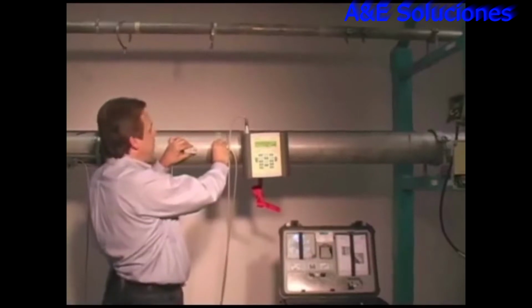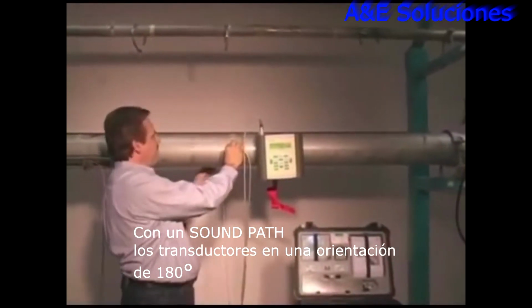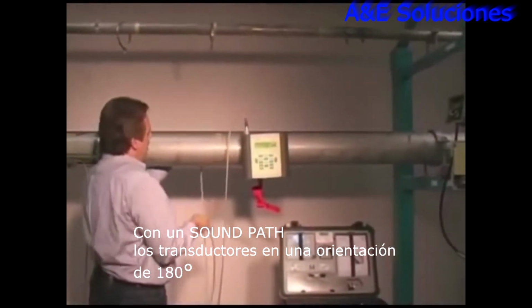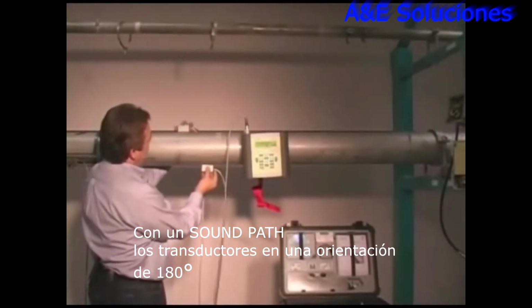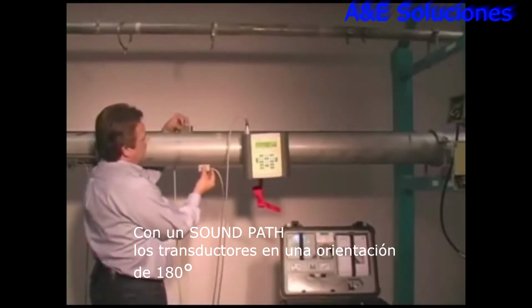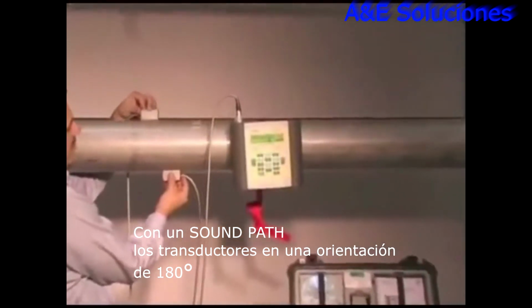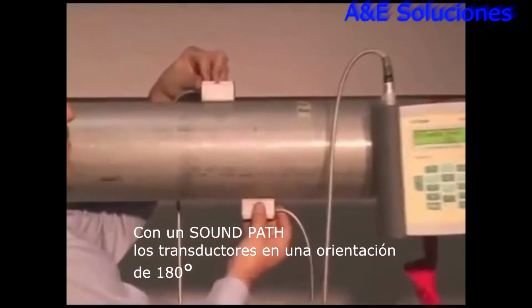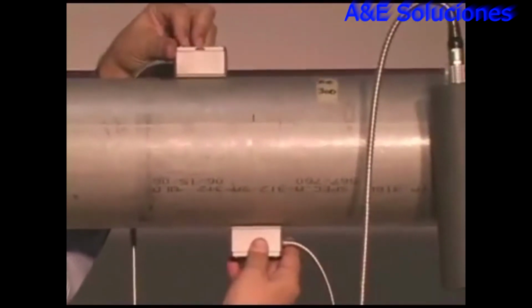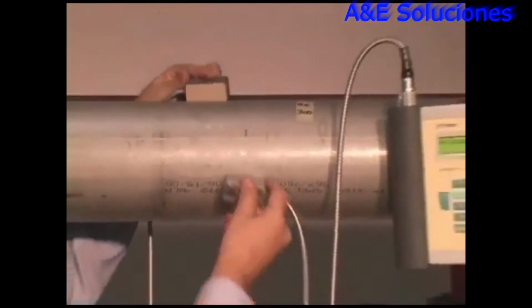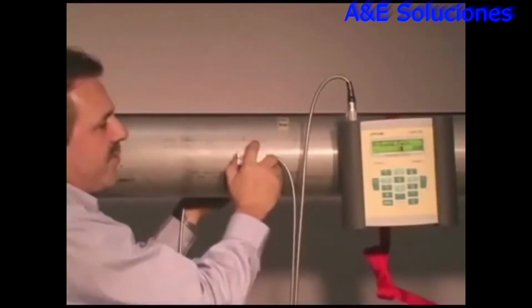One sound path would be where the other transducer is on the opposite side of the pipe. Let me show it to you like this so you can see it. That would be one sound path. We typically don't want to mount on the top and bottom of the pipe, because if there's any air in the pipe, it tends to cling to the top of the pipe, right? So it would be something like this.